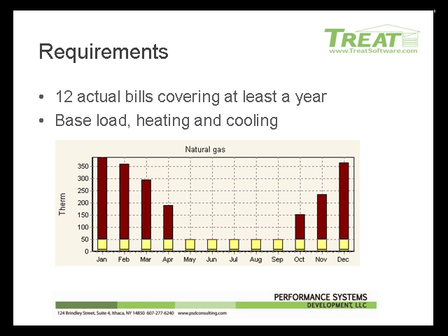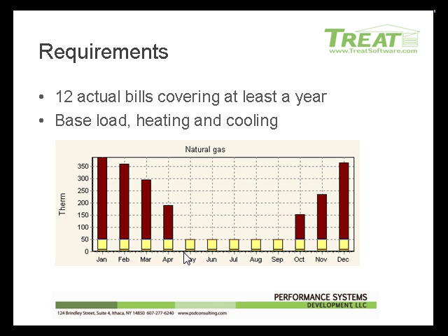Before you get started, it's important to be sure you have a large amount of reliable data available in order to get meaningful results. We recommend that you have at least 12 actual utility bills available, covering at least a year for each analyzed fuel. The software is trying to determine base load as well as heating and cooling use from the bills you have entered. So if a fuel is used for both HVAC and base load use, it's important to be sure you have at least a few months available without any noticeable heating or cooling use in order for the software to determine base load.